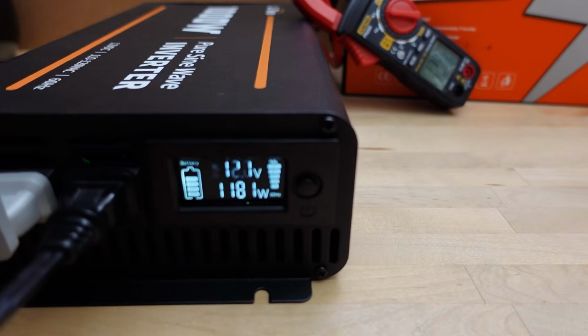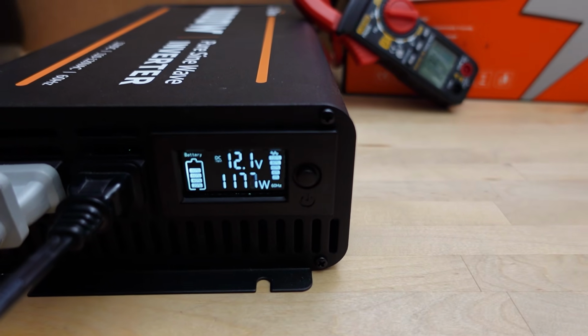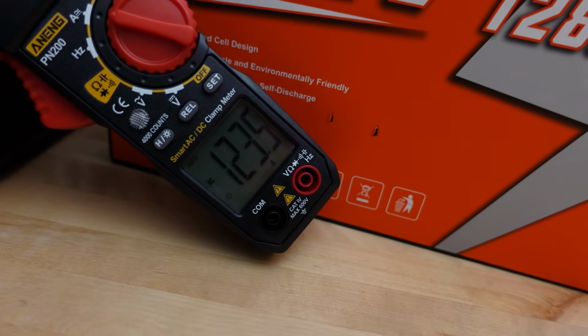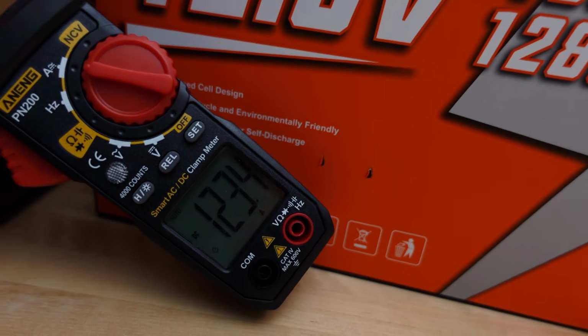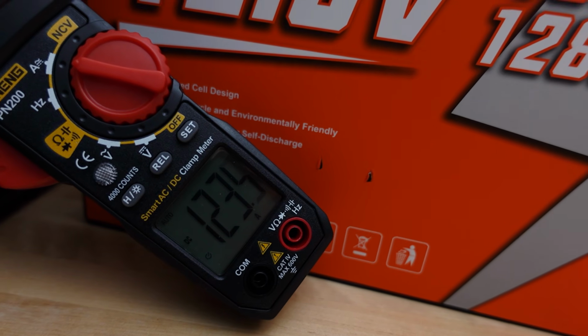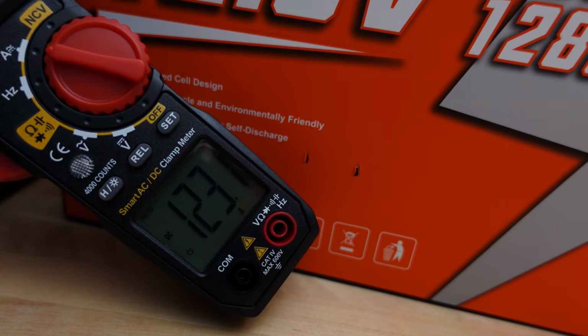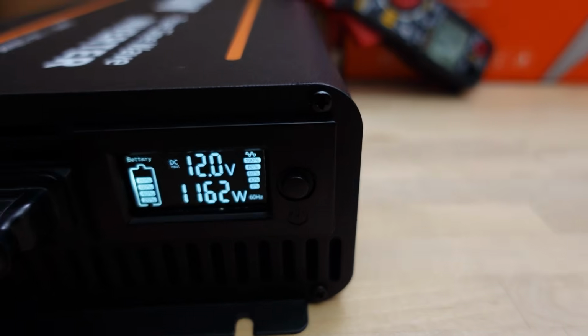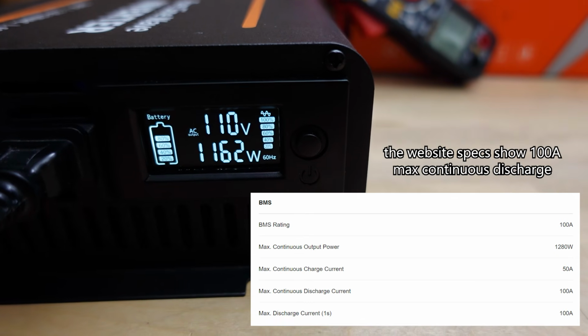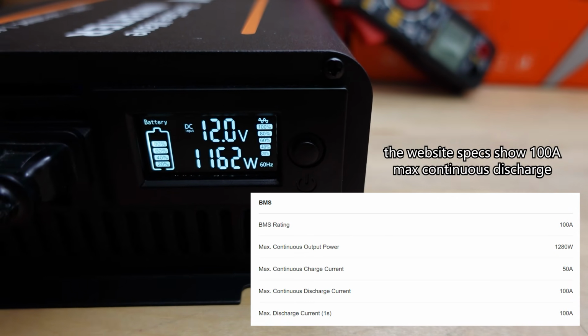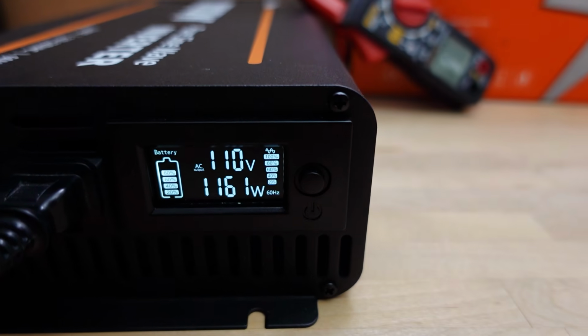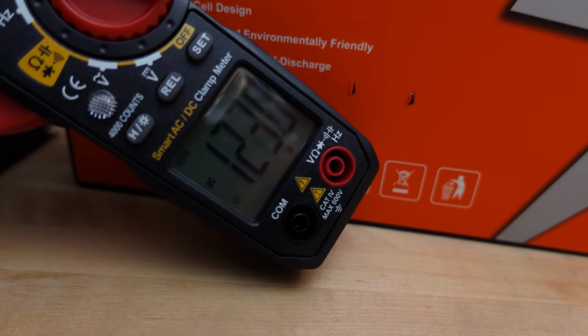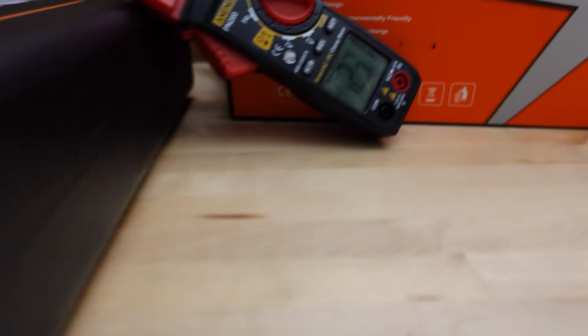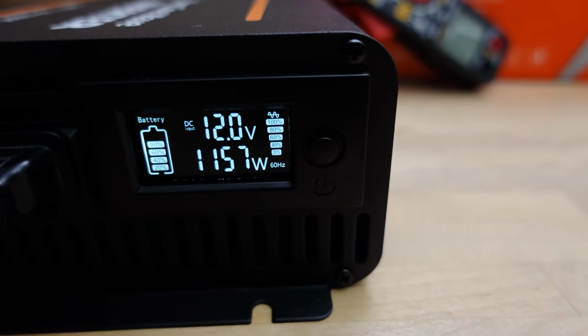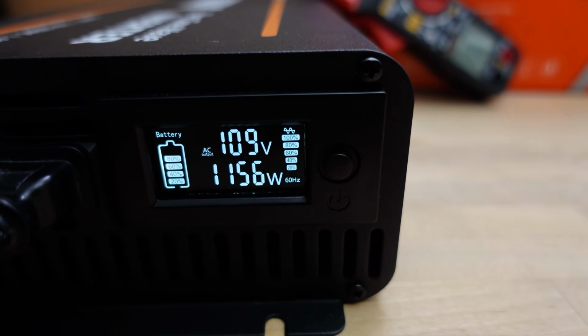The BMS is able to go to 125 amps. Usually that's just normal. But because this battery says it's rated to 100 amps, I would think that the max overcurrent protection would kick in, but apparently it must be rated for more than that. So either the documentation is outdated, perhaps, or it's just using the same kind of BMSs that are in a lot of these 100 amp hour batteries, and they can go up to 200 or 300 amps. Typically what happens is as the current draw goes higher and higher and you start getting closer to 200 amps, 300 amps, the BMS starts getting very warm, and then the over temperature protection kicks in and shuts the BMS off, which cuts off the power from the battery.